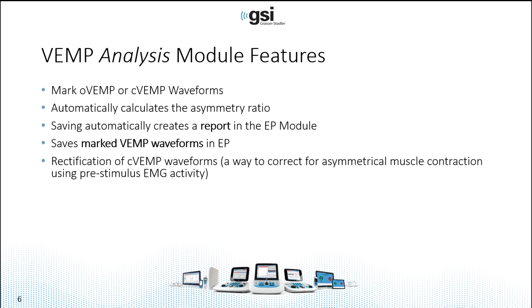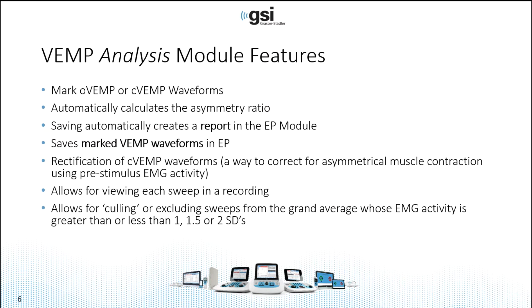The VEMP analysis module also includes the ability to use rectification, which is a way to correct for asymmetrical muscle contraction during C VEMP collection using pre-stimulus EMG activity. It also allows you to view each sweep in the recording and the ability to cull or exclude sweeps — either manually or automatically — from the grand average based on standard deviation from the mean EMG activity. I'll show you that in a moment.